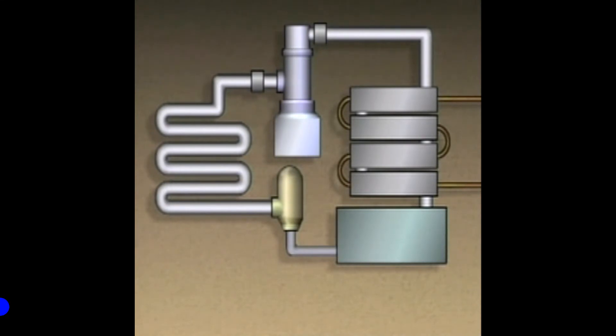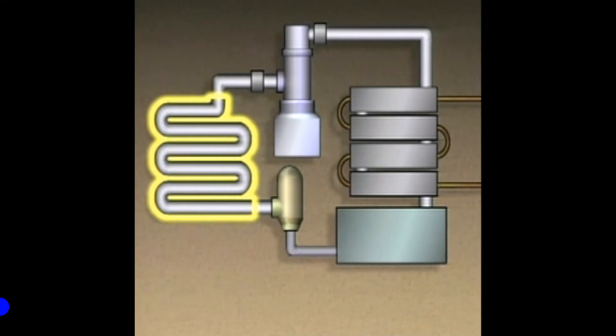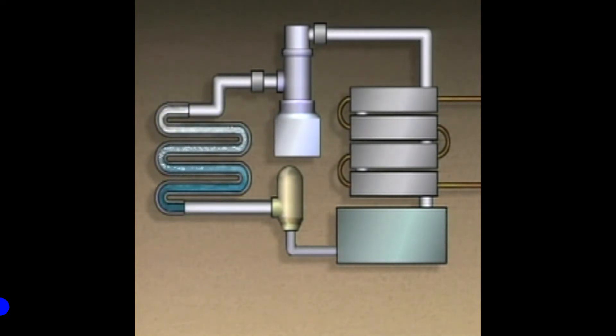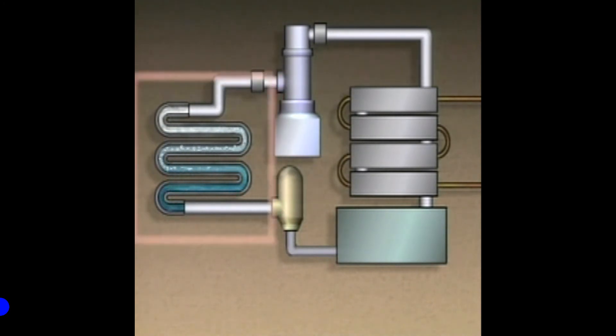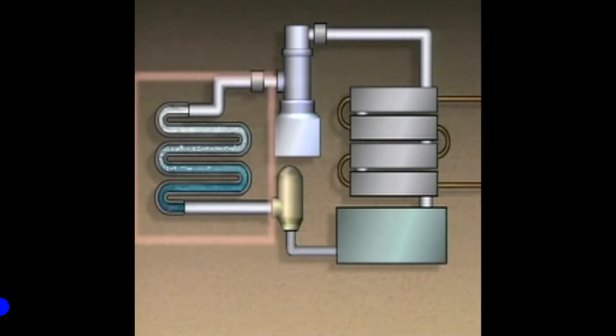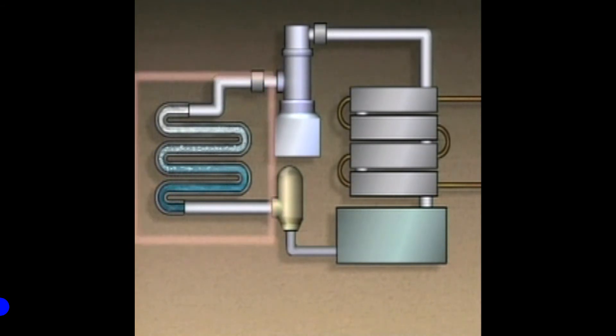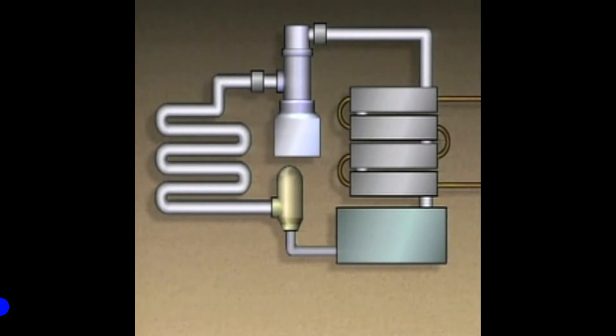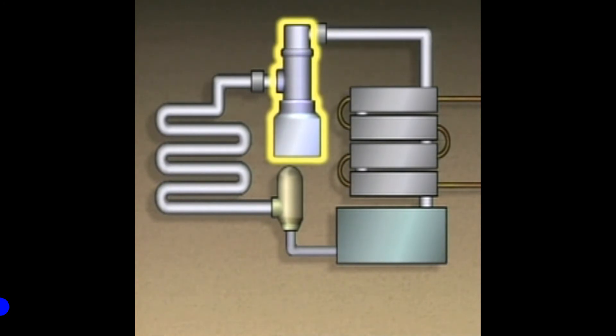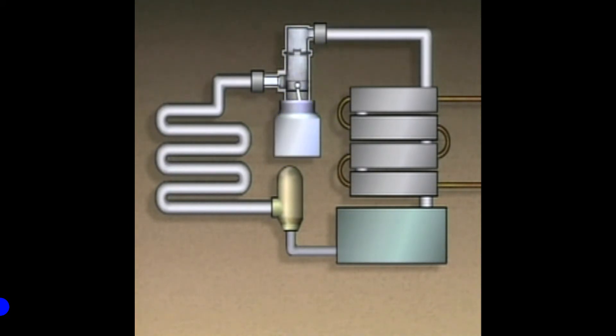In a vapor compression refrigeration cycle, the component in which the refrigerant absorbs heat is an evaporator. In the evaporator, the refrigerant evaporates or boils into a vapor, and at the same time the area around the evaporator is cooled. The evaporator draws heat from its immediate surroundings; this heat is transferred to the refrigerant because the temperature of the refrigerant is lower than the temperature of the evaporator's surroundings. To move the refrigerant through the cycle, a compressor is used to add energy to the refrigerant. The compressor receives the refrigerant vapor from the evaporator and compresses it, increasing the vapor's pressure and temperature.